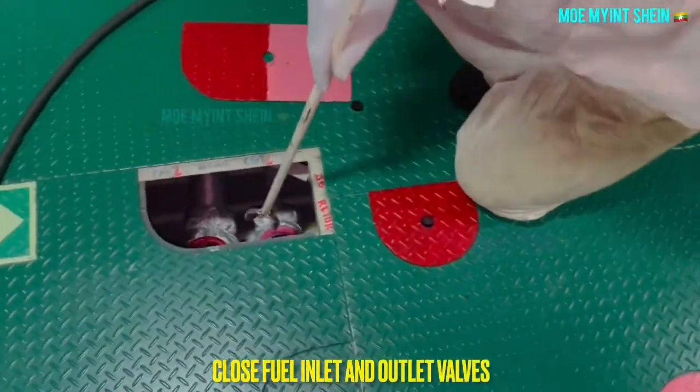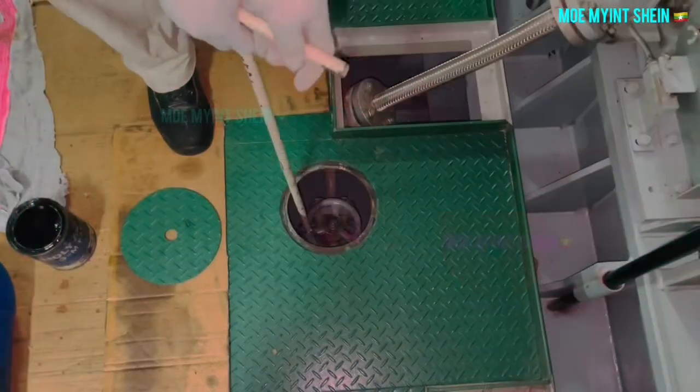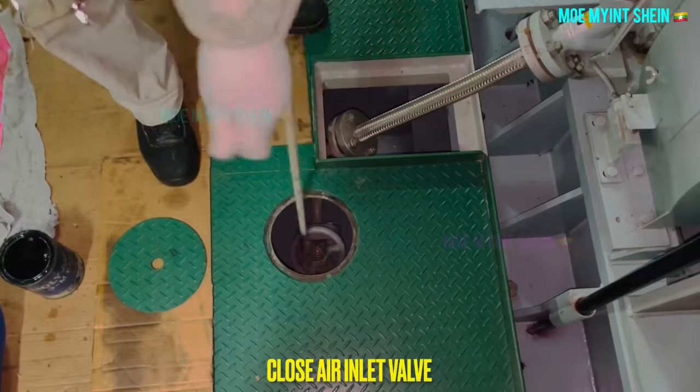At first, ensure the fuel handle is in the stop position. Close the inlet and outlet fuel valves for the constant generator engine. Close the air inlet valve and secure the starting arrangement of the generator.